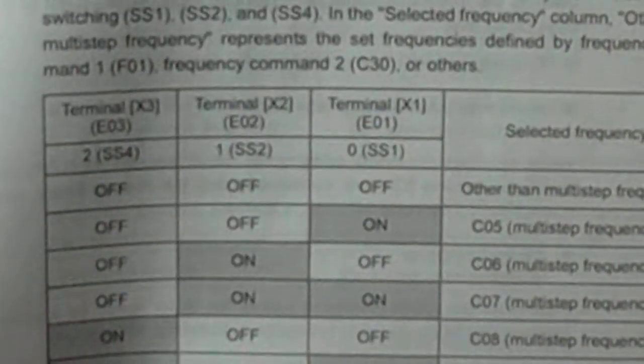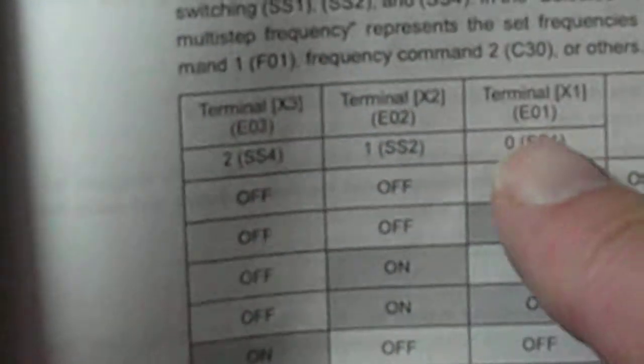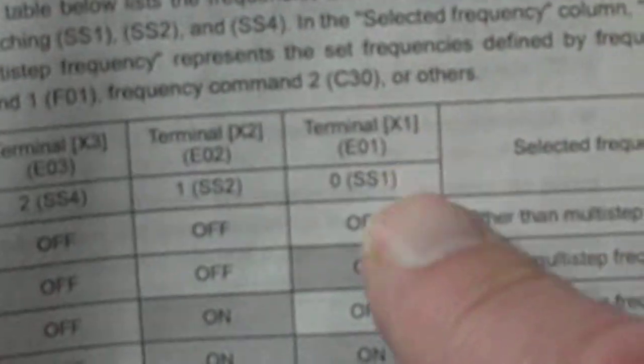So X1, X2, and X3 need to be set to two, one, and zero respectively. So terminal one, which is X3, goes to two, X2 goes to one, and X1 goes to zero. So we need to go into E01 to E03.